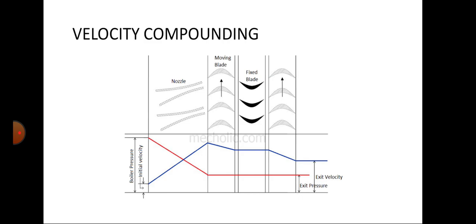Moving on to the moving plate: the steam enters the moving plate, which has to rotate in order to make rotational energy possible. It absorbs energy from the high-velocity steam. Once the velocity is at its peak at the entry of the moving plate, the kinetic energy gets carried away by the moving plate, so the velocity decreases in the moving plate while pressure remains constant. The steam next moves to the fixed plate, where both velocity and pressure remain constant. Then the steam flows to the next set of moving plates, where velocity decreases again and pressure remains constant.